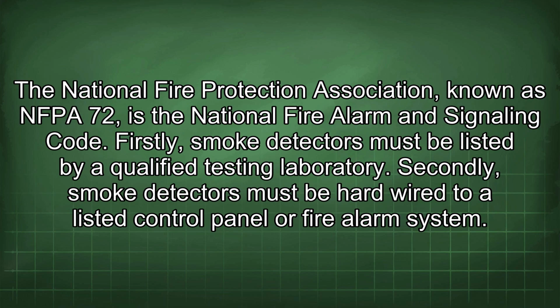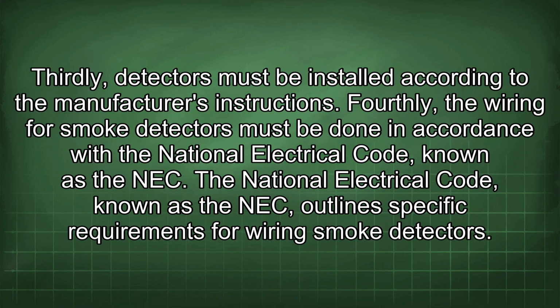NFPA 72, from the National Fire Protection Association, is the National Fire Alarm and Signaling Code. Firstly, smoke detectors must be listed by a qualified testing laboratory. Secondly, smoke detectors must be hardwired to a listed control panel or fire alarm system. Thirdly, detectors must be installed according to the manufacturer's instructions. Fourthly, the wiring for smoke detectors must be done in accordance with the National Electrical Code, known as the NEC.